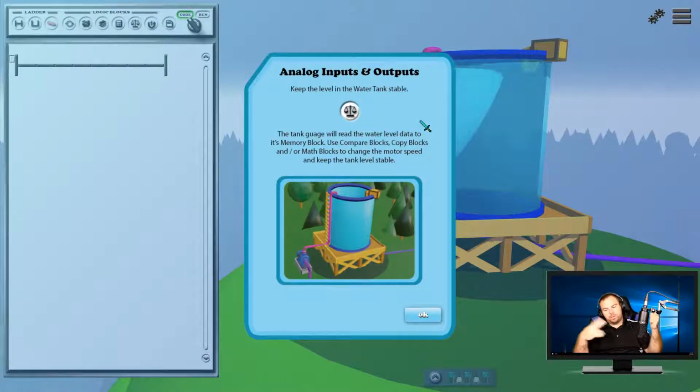It was supposed to alternate between the 2 pumps every time. But say pump 1 was assigned, but we got down to the low sensor. What would happen is the low sensor would say, hey, pump 1's obviously not working, I'm going to flip you over to pump 2. So pump 2 is going to try running. If that low sensor doesn't get triggered after so long, then an alarm sounds saying, hey, both these motors are having a fault, so I need you to do something about it. Get over here, check this sensor, check out these motors.